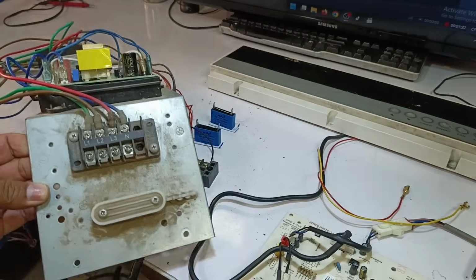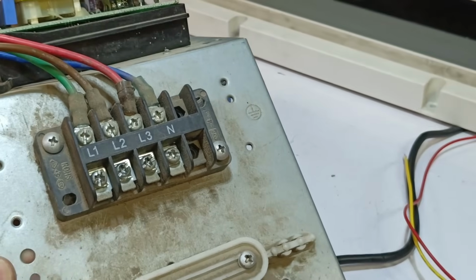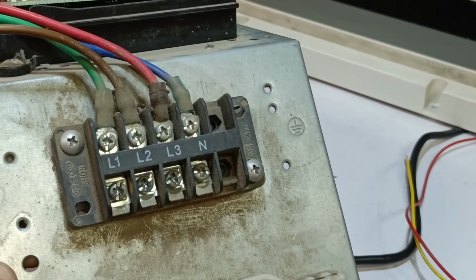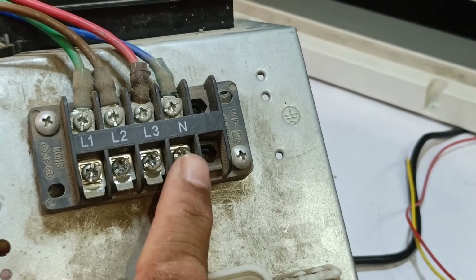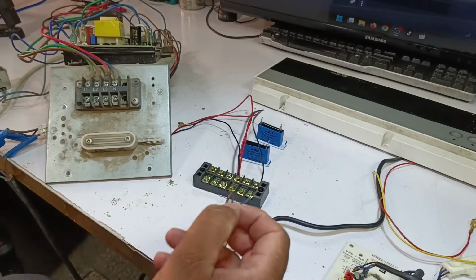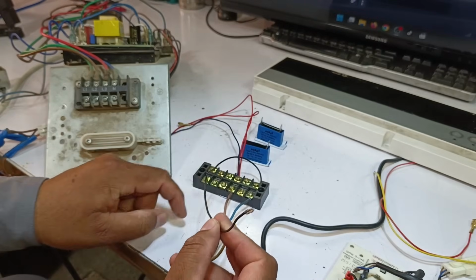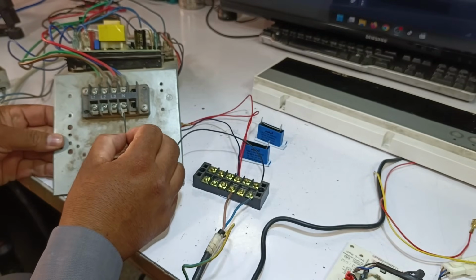At this point, some of the connections have been completed. When we look at the outdoor PCB, you can see that we need to provide connections for line 1, line 2, line 3, and neutral. Now, what we have to do is connect the neutral wire we previously prepared directly to the neutral terminal.